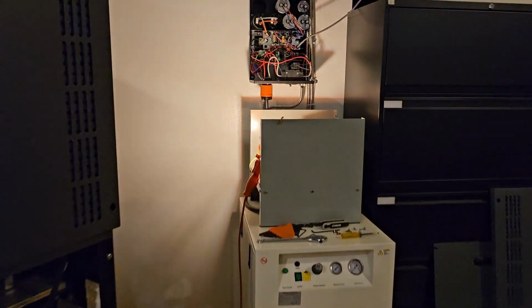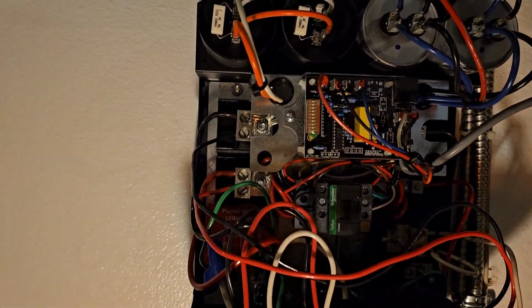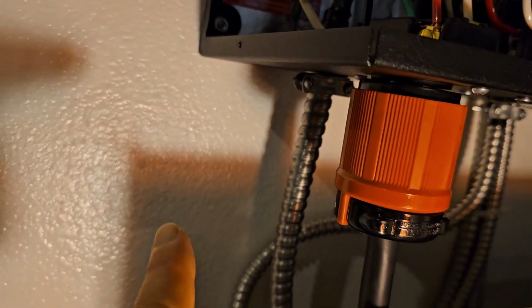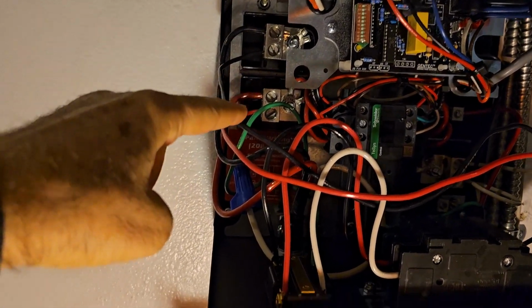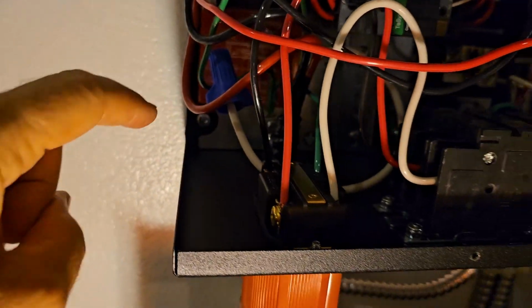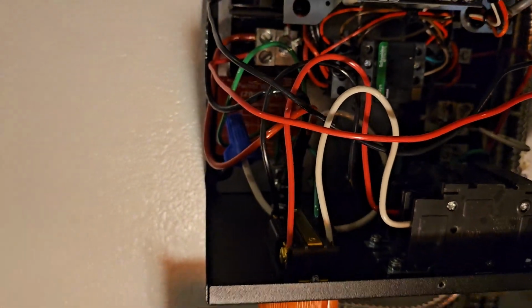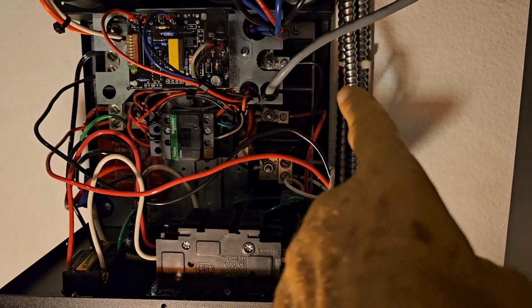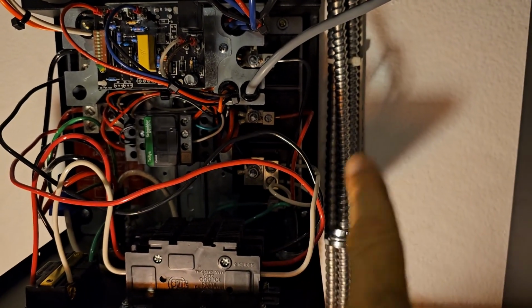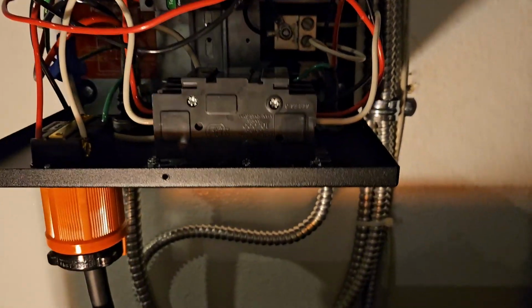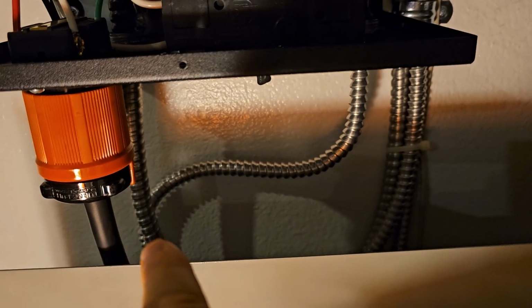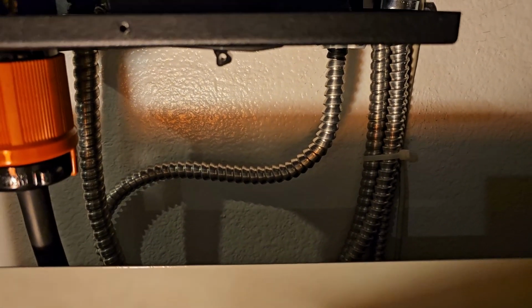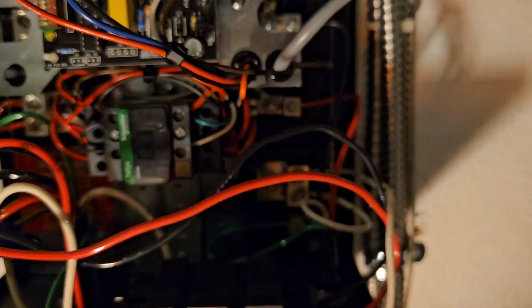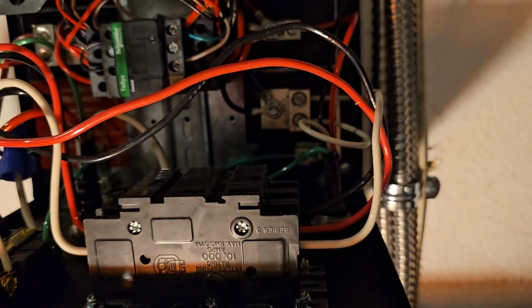Here's what happens. The three-phase panel gets a 240 volt line that comes in underneath the machine. There's black, there's red. The white wire isn't used from here, it's capped off. And then there's the ground. It goes through the system and out the other side comes a 240 volt line - a black, a red, and a white wire. This wire goes through to the idler motor across the shop - that's the manufactured line, 240 volts being fed to that motor. As the motor turns, it generates a third phase, and that's on the white wire.